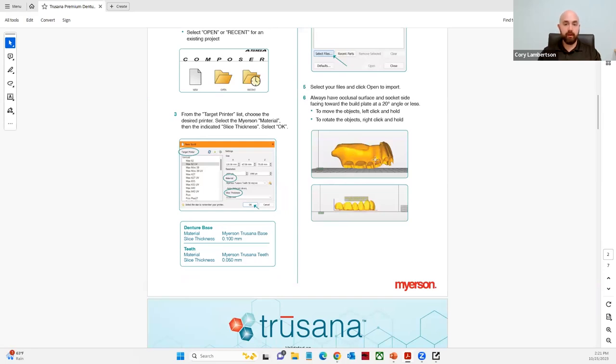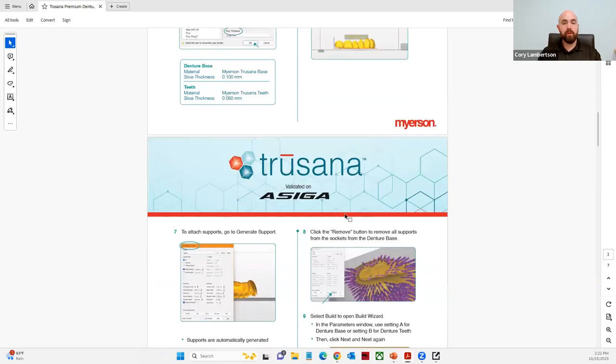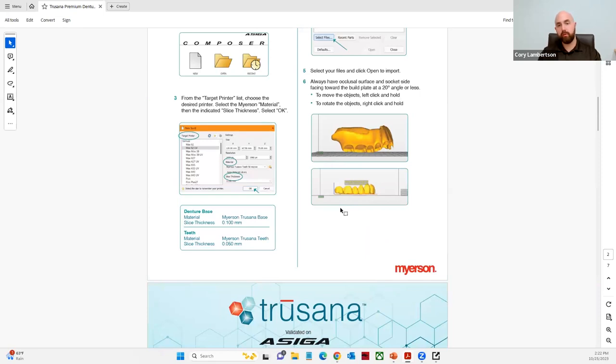For the denture base resin, the instructions recommend placing it with the socket side facing the build platform at a 20-degree angle. I did have communication with one of the engineers working with Myerson, and they said the 20-degree angle can be adjusted — if you want them more vertical, you potentially could. They are doing more studies on that, so be on the lookout. If they do approve that angulation, they will update it into the instructions for use.